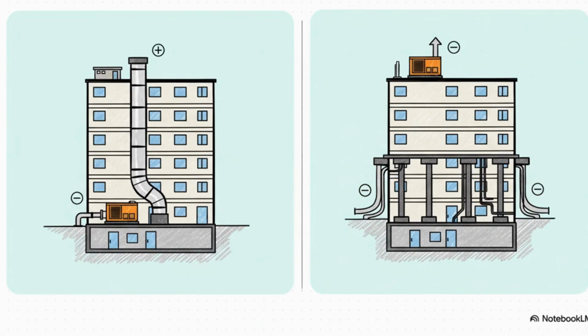You've basically got two choices: basement or rooftop. Do you put it in the basement? That's great for running fuel lines, but then you need these enormous ducts, we're talking 4 square meters for a decent-sized set just to suck in enough cooling air. Or do you put it on the roof? That's perfect for air and exhaust, but now you have to structurally reinforce the entire building just to hold its immense weight, not to mention running gigantic power cables all the way down.